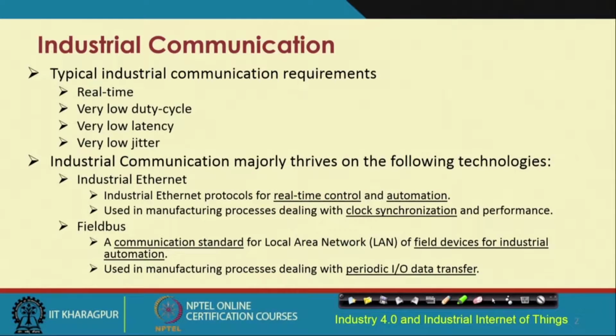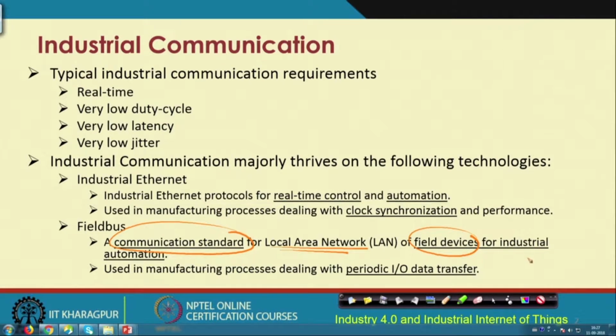So, industrial Ethernet, and the next one is basically the field bus. In the field bus technology, we are talking about having some kind of a communication standard for use with local area networks, having connectivity with the different field devices, field instruments in the industrial automation sector. Field bus technology is primarily used for manufacturing processes dealing with periodic input output data transfer. So, these are the two main technologies that have been used in the industrial communication sector so far.